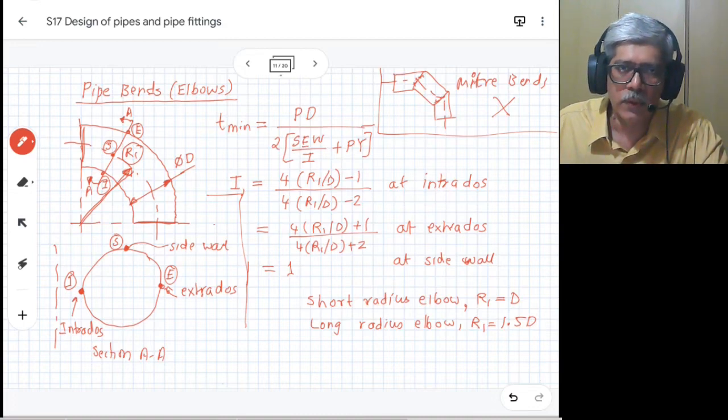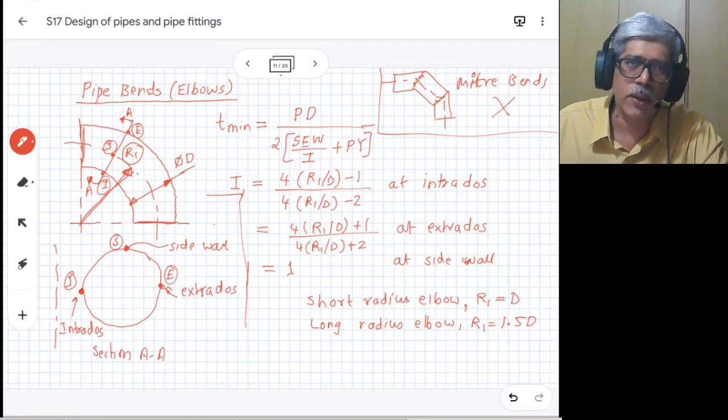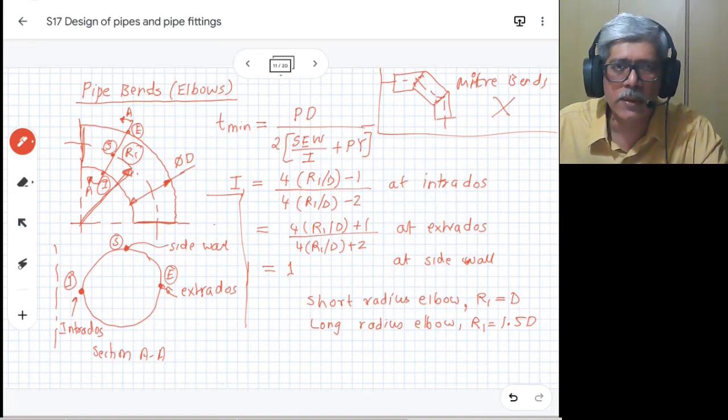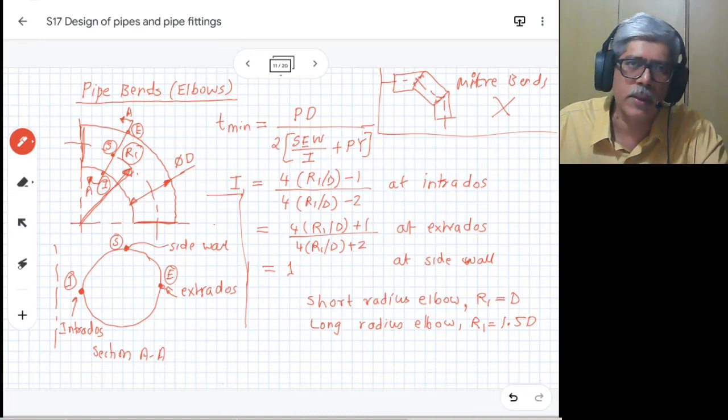The short radius elbow will have two costs associated with it: one is the required thickness will be more, and secondly, the flow losses in the flow will also be more because of the sharper change in the velocity.